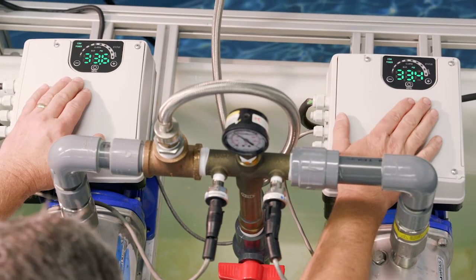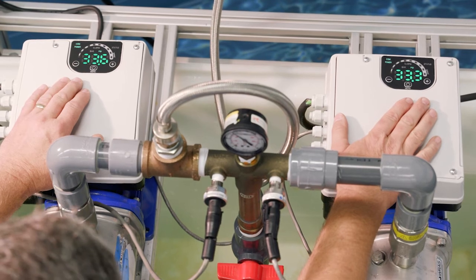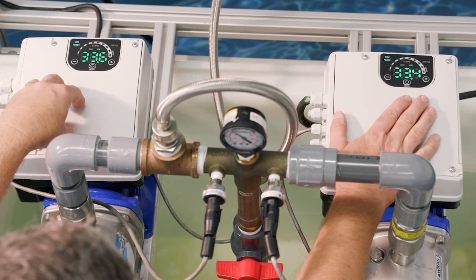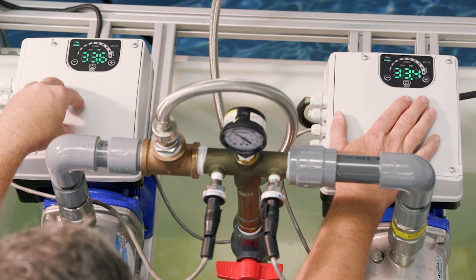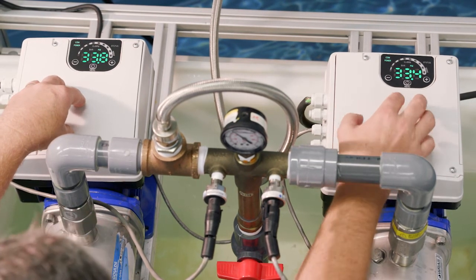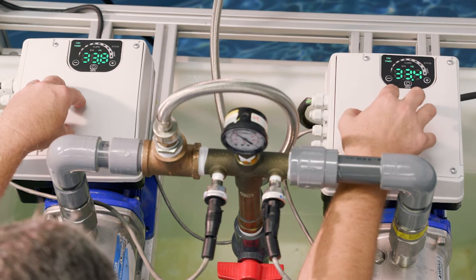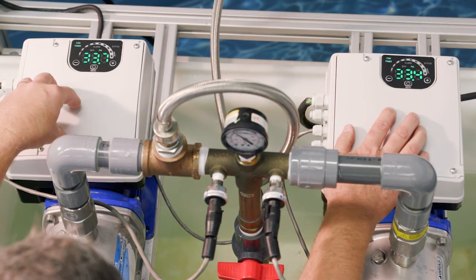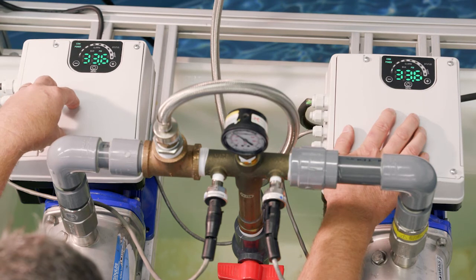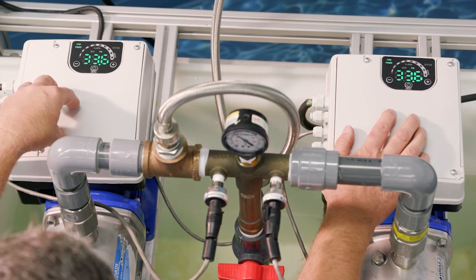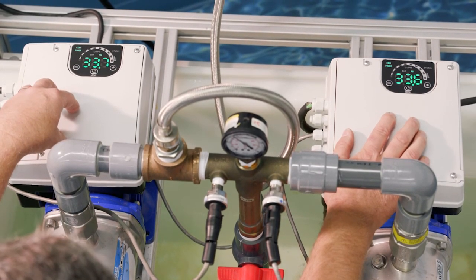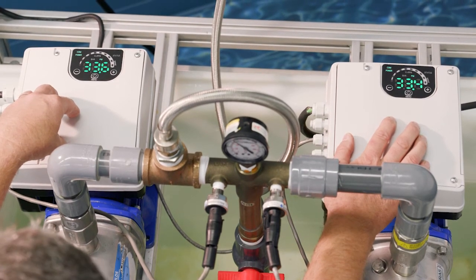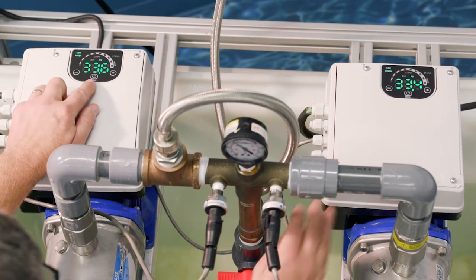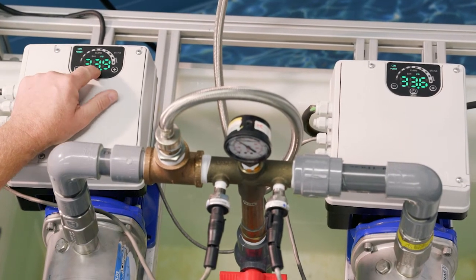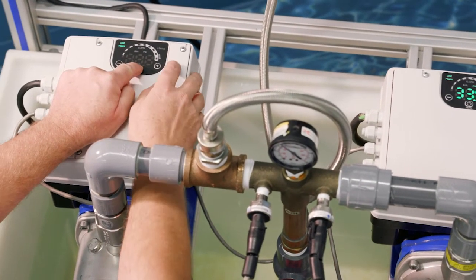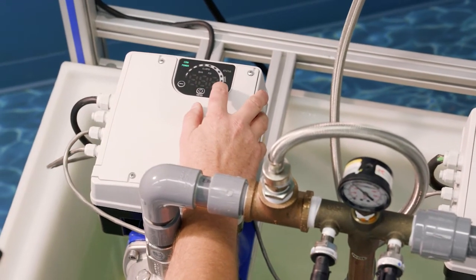And when it cannot keep up with the demand at full speed, it calls for your lag pump to come on. And what's different about this is your lead pump is going to operate at full speed, and then your lag is going to vary. So that would be the difference between synchronous and serial cascade. So let's go to the parameters here, and let's just change that one parameter. So press and hold again. So now we're into the parameters.